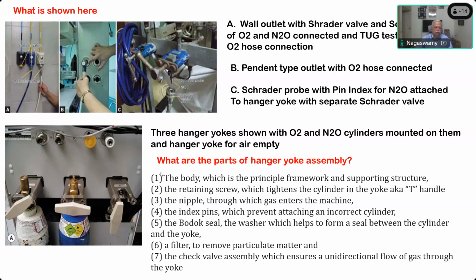So there are totally 7 components of the hanger yoke assembly: the body, the retaining screw, the nipple or the entry port, the pin index pins, and then the Bodok seal, and then the filter inside which is not visible, and the check valve again which is not visible, which will allow only the gas to go from here and not come out from the machine to the cylinder back. Okay, so all these parts you have to mention in the answer.